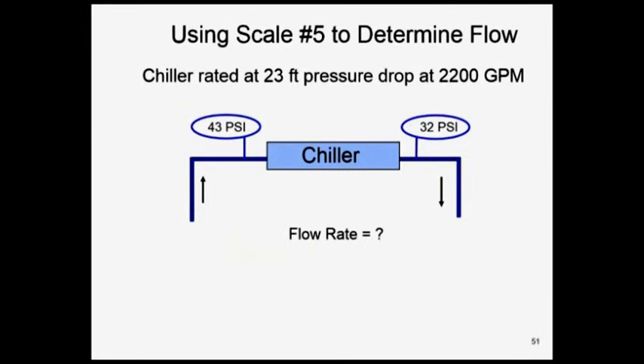Now stop right here. For everybody involved, that's a pretty tight reading of 11 pounds. I want you to take that reading with the same gauge. We would have a gauge on the inlet and the outlet of the chiller, or we should. I'm pretty sure your detail shows that. What I'm asking you to do is take the gauge on the inlet side and move it to the outlet side, and take the gauge on the outlet side and move it to the inlet side. Double check this. I am not interested in whether it's 43 pounds or 32 pounds. I'm interested in the pressure drop. All I want is an accurate pressure drop. I don't care what the actual pressure is. I want the pressure drop.